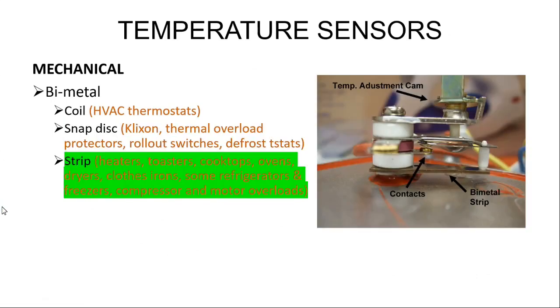Okay, bimetal strip thermostats. Used in heaters, toasters, cooktops, ovens, dryers, clothes irons, some refrigerators and freezers, and also used as compressor and motor overloads in some cases. It shows a temperature adjustment cam, which is adjusted by a rotating stem. You have a set of contacts and a bimetal strip. The cam could be set so that the bimetal strip would have to be a greater degree or a lesser degree based upon the desired setting in order for the contacts to open or close, depending on how it's designed.